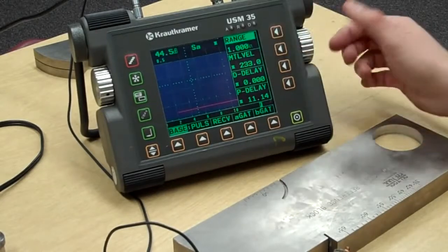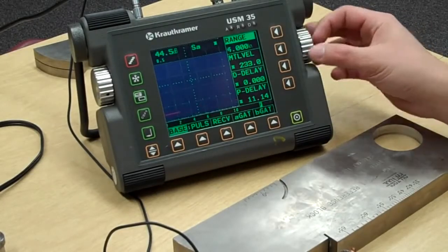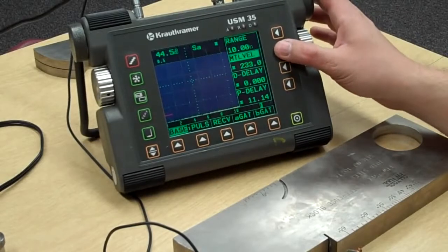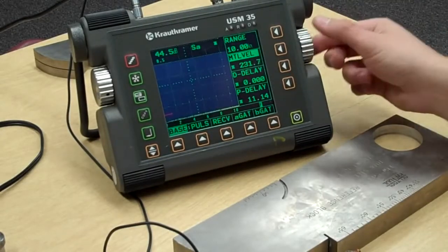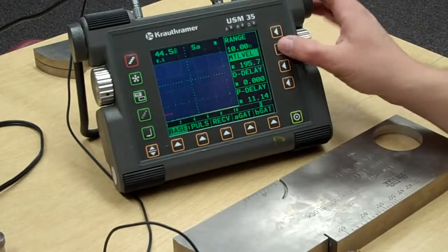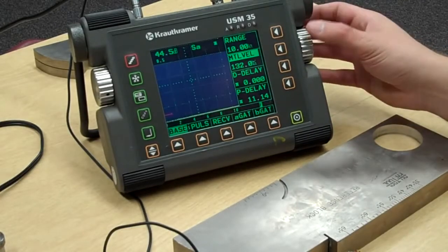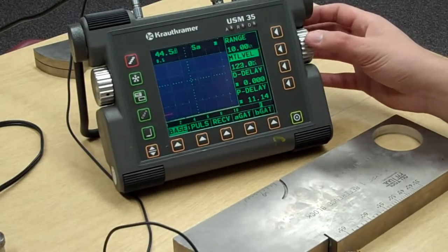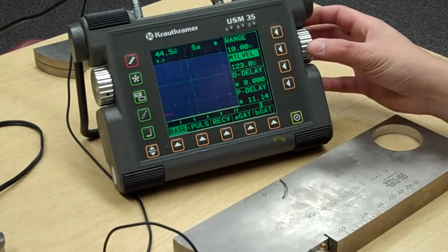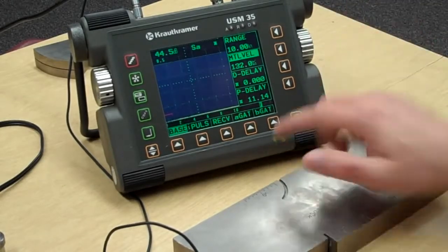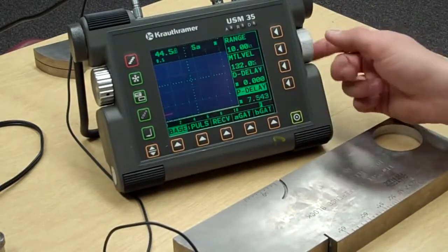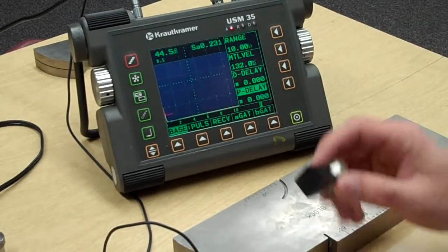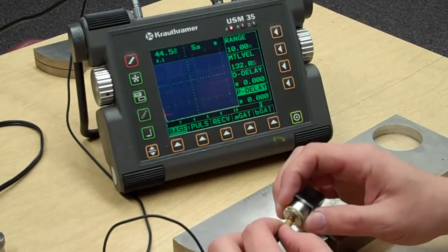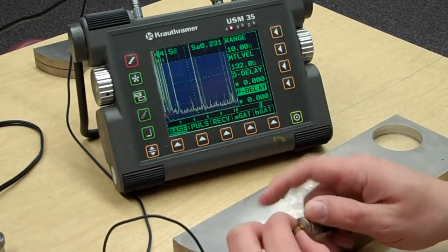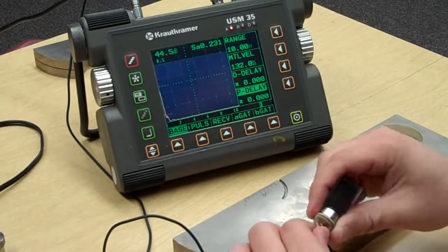So, before we ever hook the transducer up, I'm going to take my range up to 10 inches. Okay? My material velocity down to shear wave, which if I push that again I could do that. We're going to be right in here between one of these two. If I'm remembering right, it's going to be about right there. And then we'll bring our probe delay all the way back to 0. There's our initial pulse. Here's our hookup. Just going to hook this guy up so we know it's alive. Okay? Maybe. There we go.